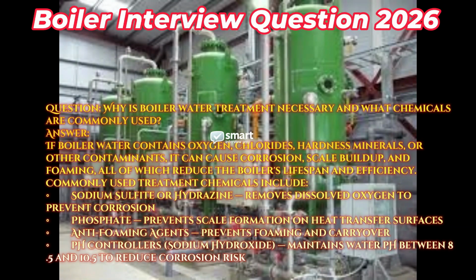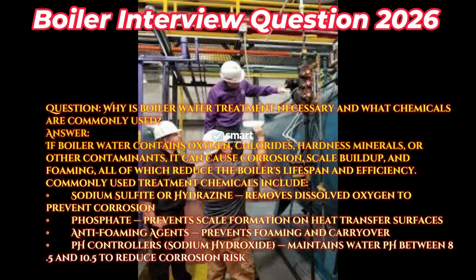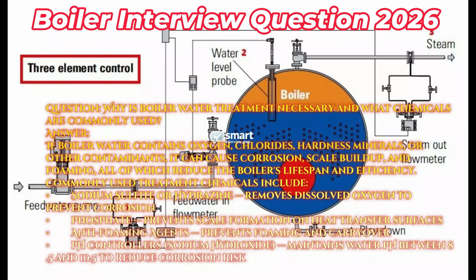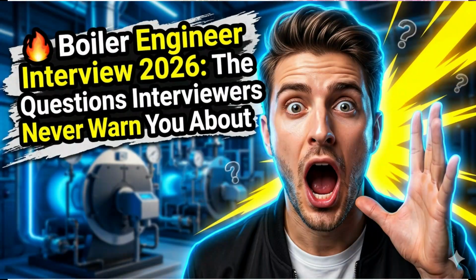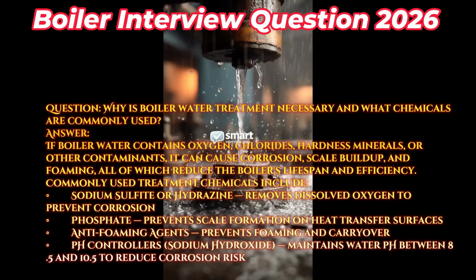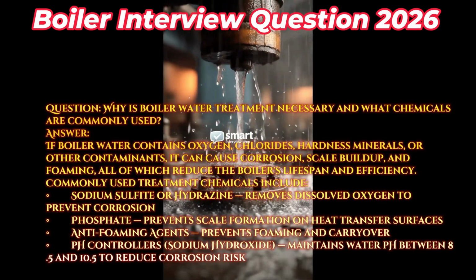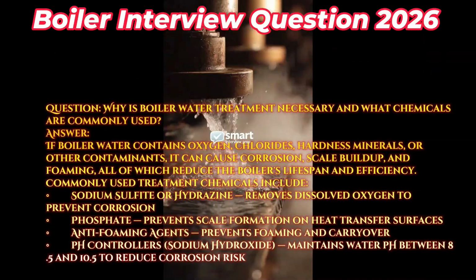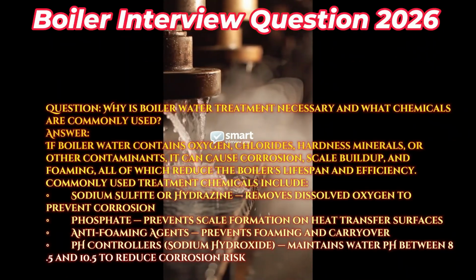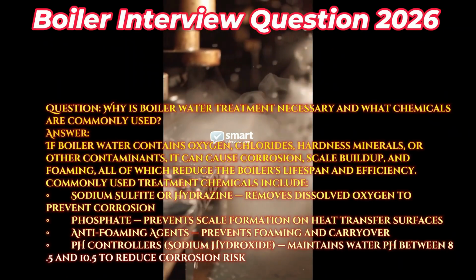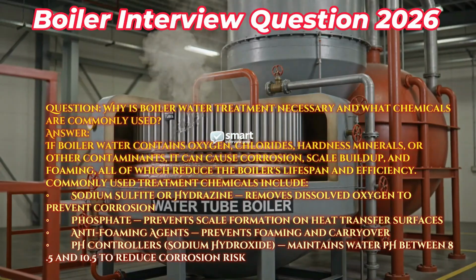Question: why is boiler water treatment necessary and what chemicals are commonly used? Answer: if boiler water contains oxygen, chlorides, hardness minerals, or other contaminants, it can cause corrosion, scale buildup, and foaming, all of which reduce the boiler's lifespan and efficiency. Commonly used treatment chemicals include sodium sulfite or hydrazine, removes dissolved oxygen to prevent corrosion. Phosphate prevents scale formation on heat transfer surfaces.